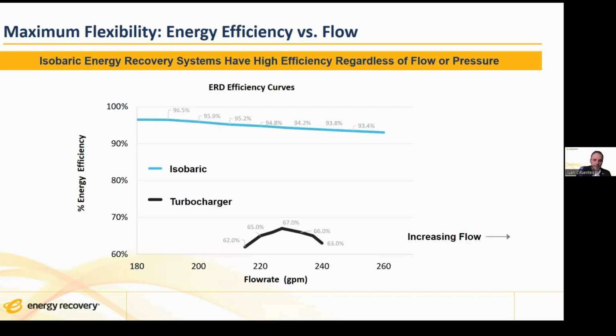Finally, regarding the PX, this is the energy recovery device that has the maximum flexibility. If we compare this device with the turbocharger, we can see that the efficiency is almost the same all around the allowable flow. However, the efficiency of a turbocharger varies a lot in the small operating range of this device. Therefore, we have much more availability of operating points with the PX.